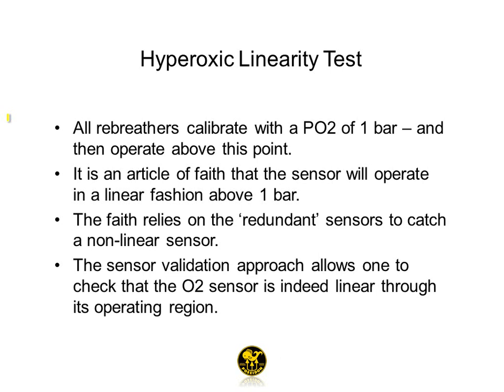With this technology, as you get down to about 6 meters, we start hitting that oxygen sensor with pure O2. And we look at its response and make sure that the damn thing is linear beyond the operating point. And if it isn't, we let you know. I'm sure if there are people in this room who have dived the rebreather, I've heard plenty of people bitching, oh, it wouldn't let me go above 1.0. Yeah, well, because we couldn't guarantee that the sensor was working properly up there. Right now, for everyone else, it's just an article of faith that it damn well works.